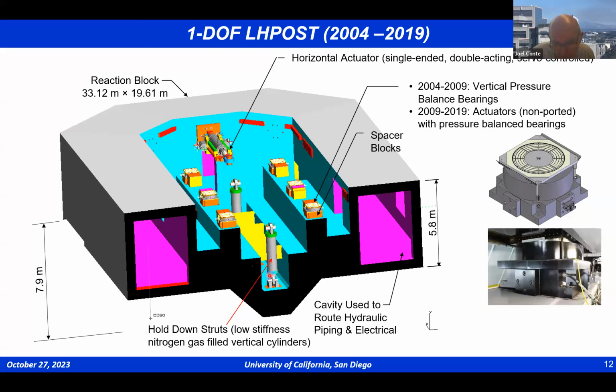You can also see these tubes here. We call them hold-down struts. They are tubes with a piston in the middle, a rod towards the bottom, and nitrogen at 2000 psi in the bottom chamber, which produces a downward force on the platen. So it's pre-stressing the platen against the vertical actuators to create the overturning moment capacity.